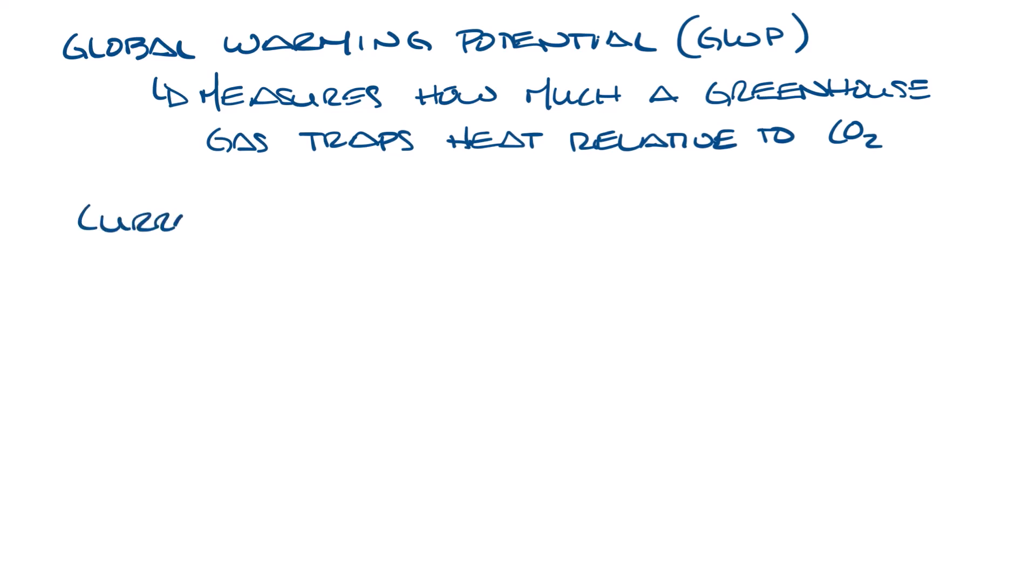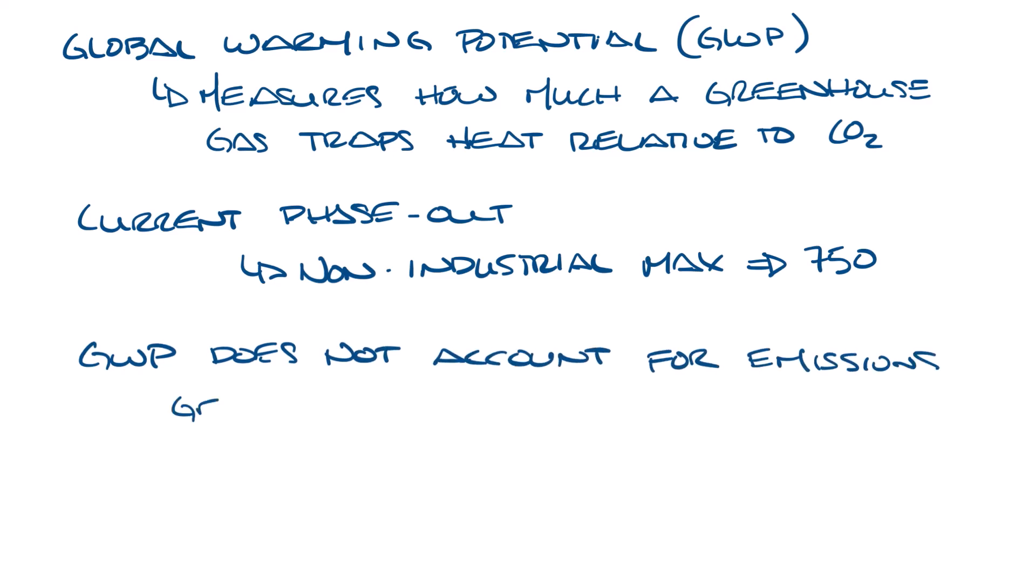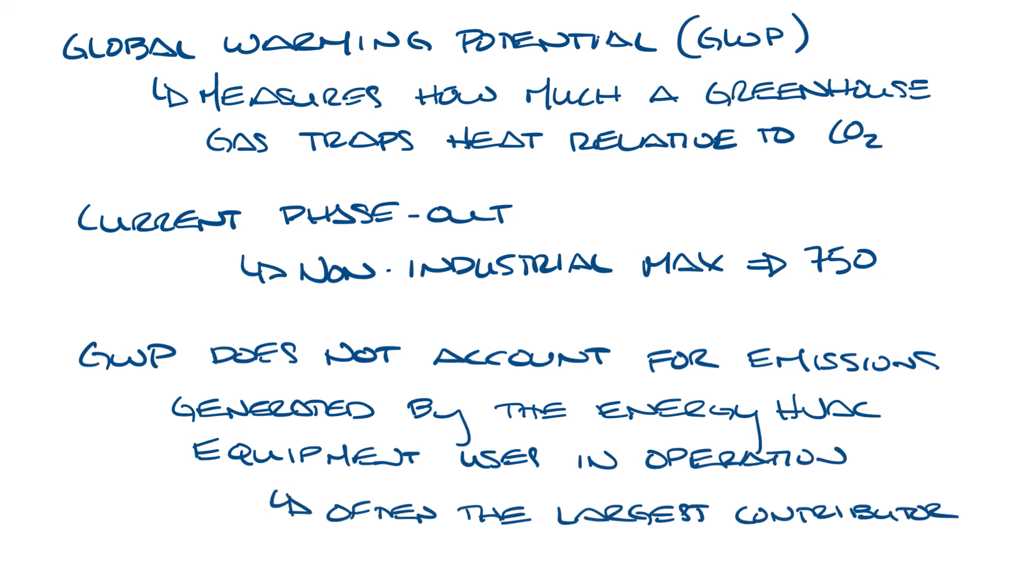The current refrigerant phase out that we're doing now sets a maximum GWP for non-industrial HVAC equipment at 750. The GWP only tells part of the story about a refrigerant's environmental impact. It doesn't account for the emissions generated by the energy HVAC systems use during operation, which is often the largest contributor to the system's overall impact.